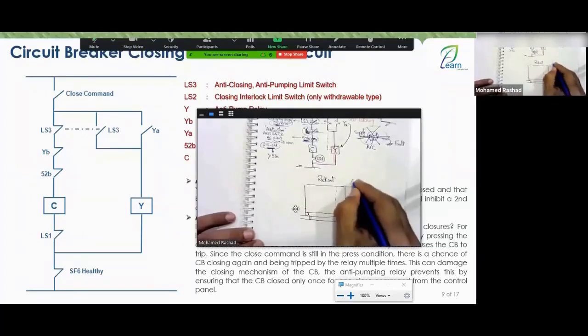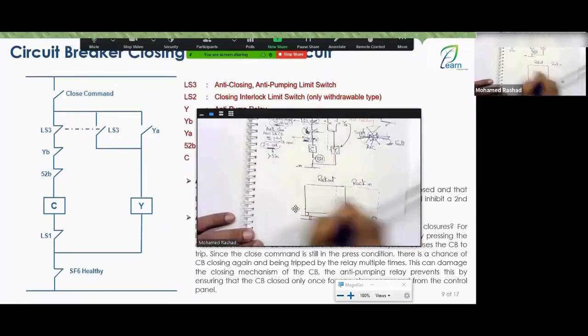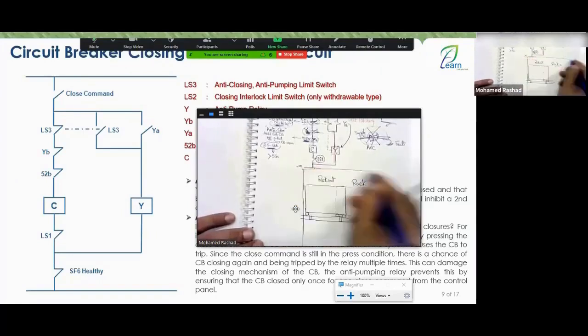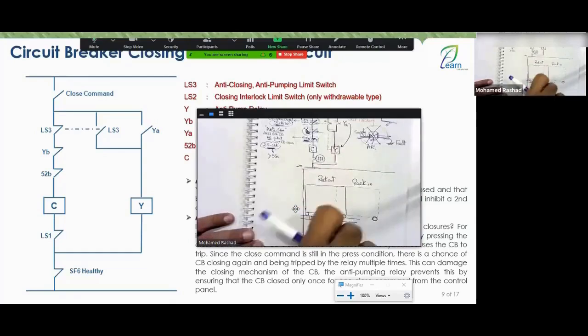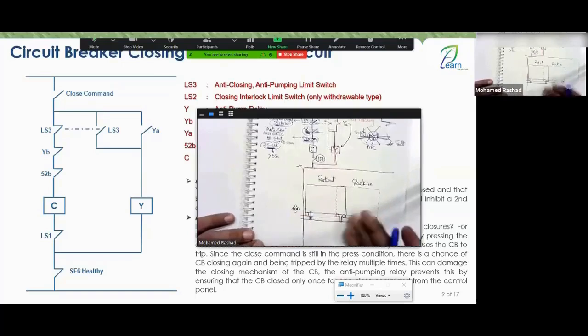So whether the breaker is rack out or rack in, here is the front of my cell. It's rack out and goes inside as rack in, or it's rack out and you came to close the electrical breaker. There's a pin here that goes down into this hole, preventing the movement of the breaker in the rack in direction. And if it is rack in and you close it, the same lever goes down here into this hole, preventing mechanical movement in the direction of rack out. So as long as the breaker is closed, its movement is prohibited, whether rack in or rack out.